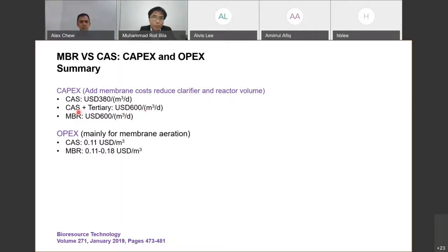And then if you compare it with MBR, the average cost is about 600 USD per cubic meter per day, which basically tells us that if you compare conventional treatment plus tertiary treatment, the investment is equal to the investment of MBR. In terms of operational expenditures, as you can see here, the efficient MBR already equals the operational expenditure of the conventional activated sludge processes.